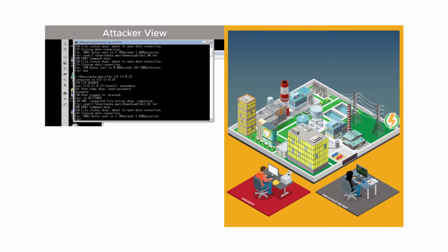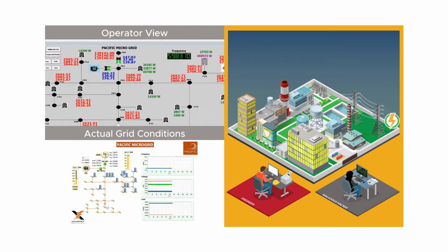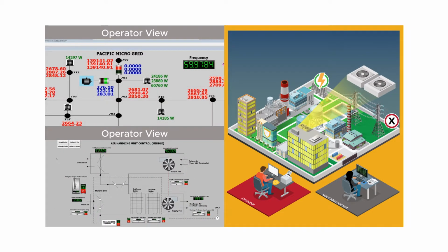He opens the relay's breaker and successfully disengages the campus from the larger grid, as we can see on our operator view and grid view. The red breaker icon indicates the campus has now been islanded, but it is still operating as a microgrid powered by a backup generator. This is indicated by a green breaker in the grid view. Systems and devices like the simulated air handler are still operating.